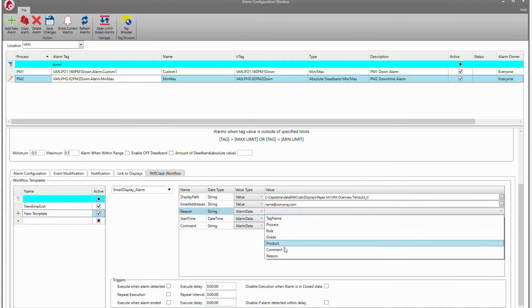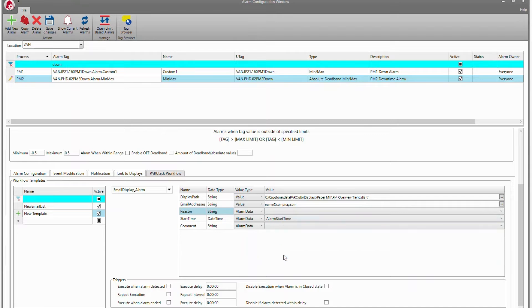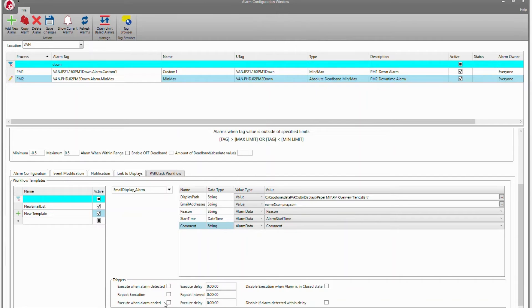We have a drop-down list based on the data type, so we can select reason and comment, and the alarm start time is already filled in for us. Lastly, we need to choose when we want this email to be sent. Since this is a summary email, we want it sent after the event is over — that way we'll more likely have our reason and comments in there. We could also add a delay if we'd like.